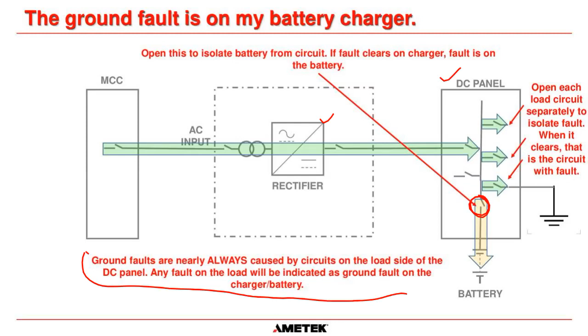This portion here, ground faults are nearly always caused by load circuits, okay? Any fault on your load circuits will be indicated as a ground fault on the charger battery, and is near enough always a ground fault on the load.